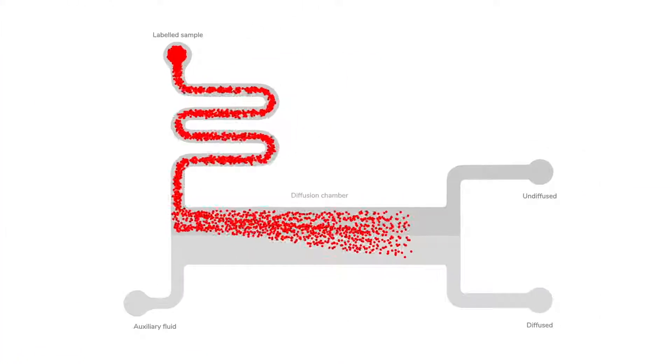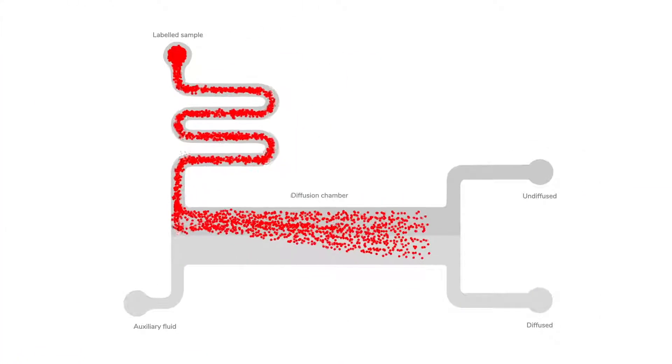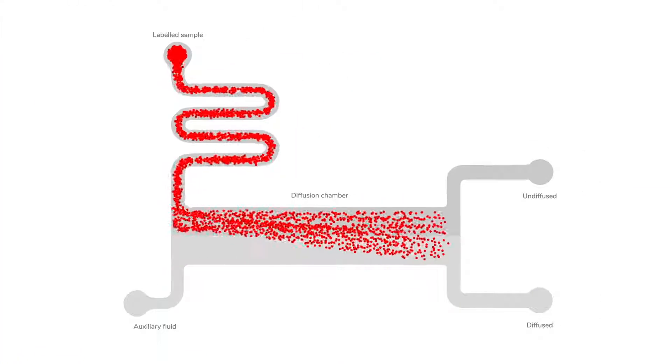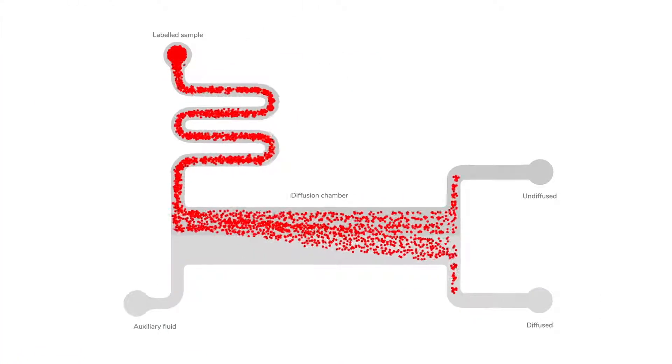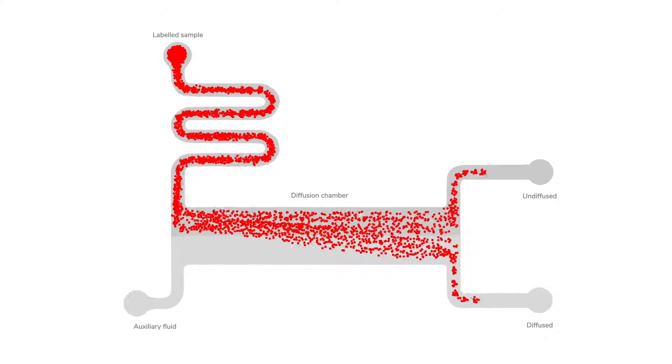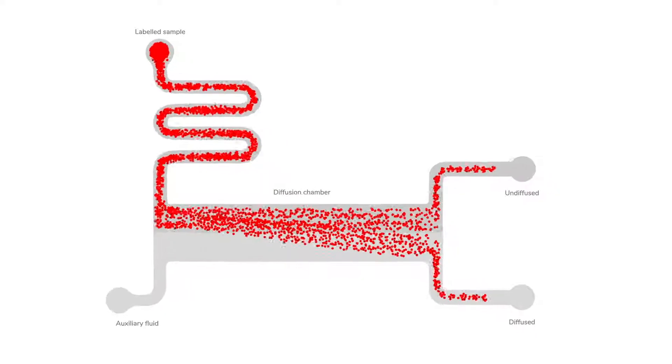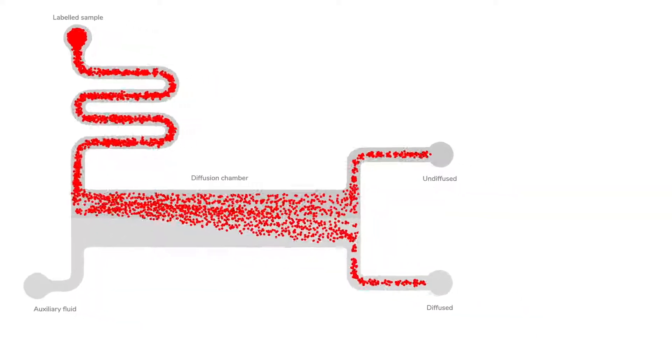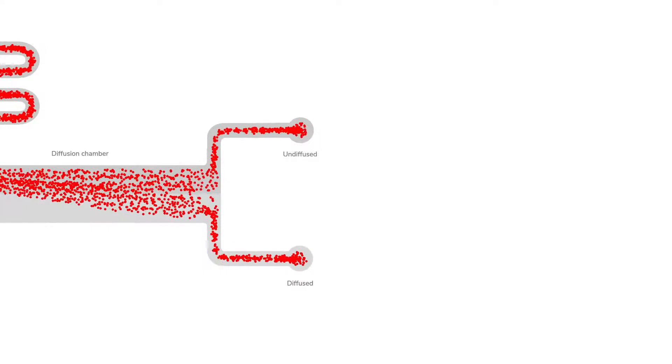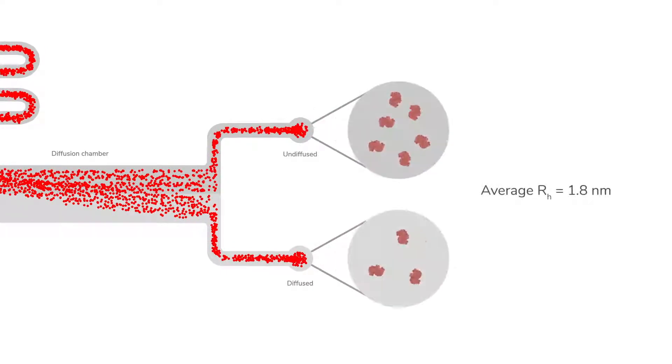At the end of the diffusion chamber the streams are split. The quantity of protein in each stream is determined by the fluorescence from the label. The ratio of fluorescence between the two streams gives us the protein's hydrodynamic radius.